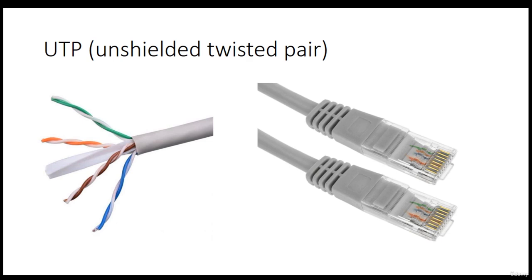reliability and efficiency. Standard factory-made cables have many fixed standard lengths like 1 meter, 3 meter, 5 meter, 10 meter, 20 meter. A UTP roll is 305 meter long and is used to make cables with lengths higher than the standard cables and is terminated by RJ45 or punched directly in the patch panel. Each UTP cable consists of 8 internal pins, branched cables shielded with a flexible PVC layer.